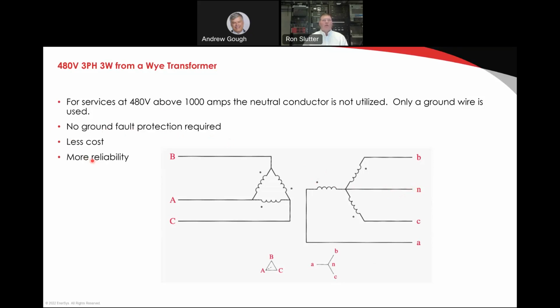So if you've ever been involved with large data center services, this is what we do for large data centers. When we go over 1,000 amps for a data center, we switch to 480 3-phase 3-wire, no neutral. And we still use a delta to Y transformer for the service. However, we don't bring the neutral into the building. Okay? Why? What do you need a neutral for in a telecommunications facility? There are only really two things that typically fall under that category potentially, and that is rectifiers and lighting. Okay, how do we get around the rectifiers? We order DC plants with 480 volt 3-phase 3-wire rectifiers, which are available. You just have to make sure that the design incorporates that requirement.